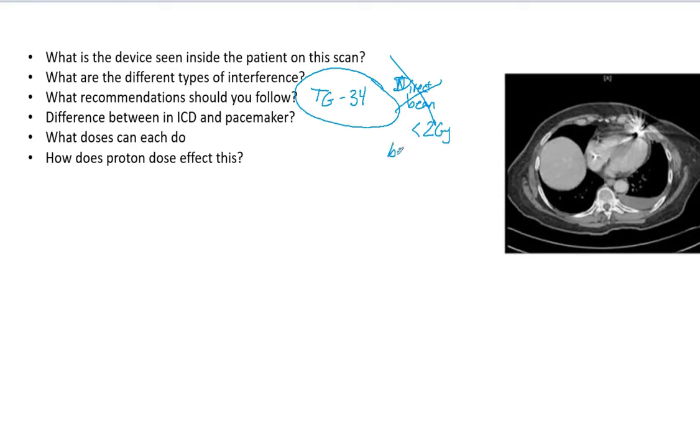First of all, you want beams below 10 MV and that's because of neutron production. You also want to avoid any type of wedges. So those are the recommendations that are ideal for you to follow. Follow TG34 as well.